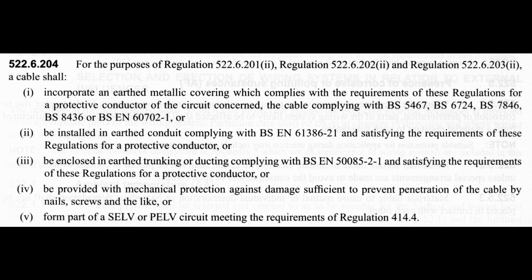It must be installed in earthed conduit, complying with that standard, or be enclosed in earthed trunking or ducting, or be provided with mechanical protection against damage sufficient to prevent penetration of the cable by nails, screws and the like, or it's forming part of a SELV or PELV circuit meeting the particular requirement.